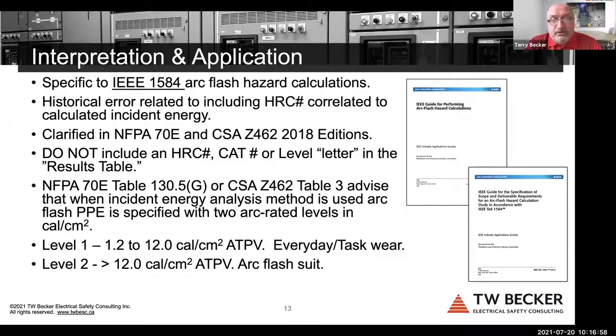So this is an ongoing project that I'll probably be working on forever, to get us off of these categories or level letters when an incident energy analysis study is completed, and we do not want to report it out. And it relates to the 40 cal myth as well. Historically, that was embedded in the power system software, and the engineer just accepted that greater than 40 cals was dangerous and no PPE exists. That was all incorrect, and I'm still seeing some issues there.